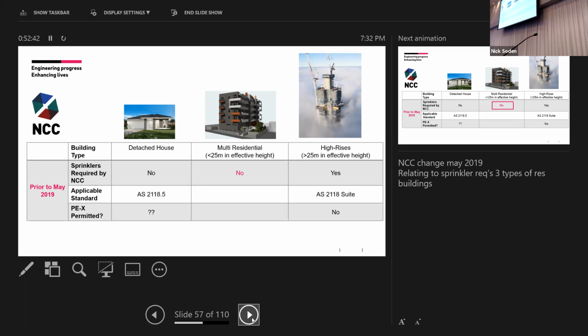So yeah, prior to May 2019, for detached houses there was no requirement for PEX and no requirement for sprinkler systems. In multi-residential, there were also no requirements for any projects less than 25 metres effective height to have fire sprinklers installed. However, our high rise comes under the AS 2118 suite of standards. Instead of dictating all the numbers, I just put the suite there. There are requirements, and PEX is not permitted on those applications.